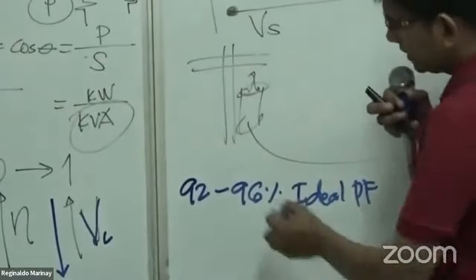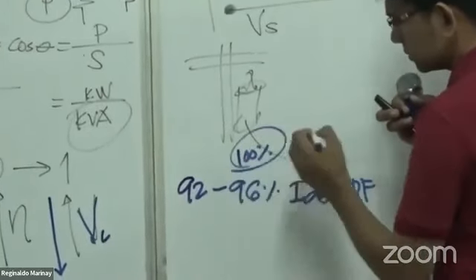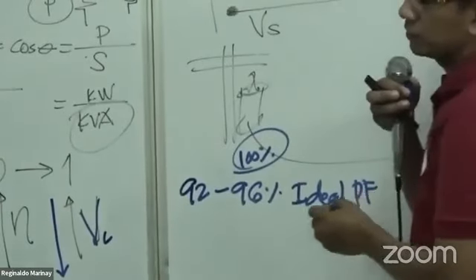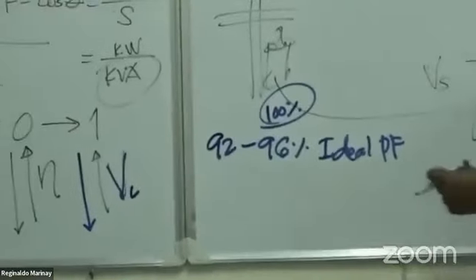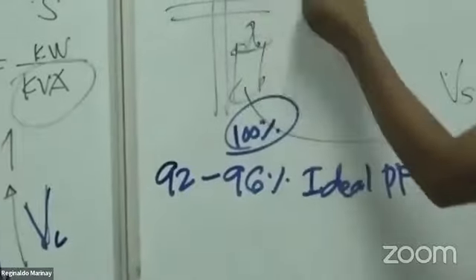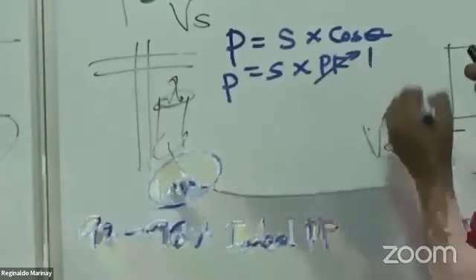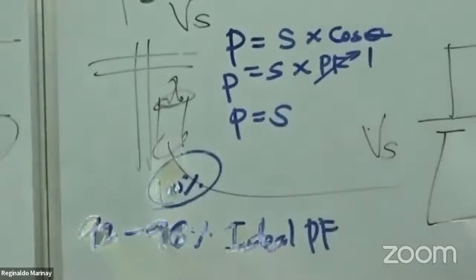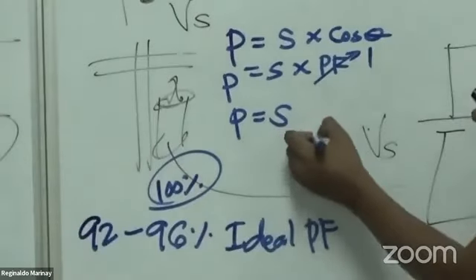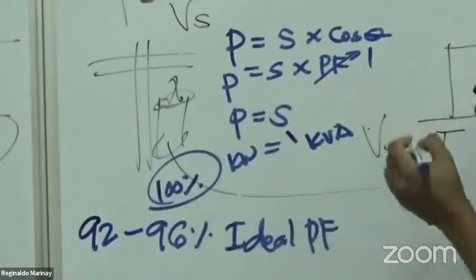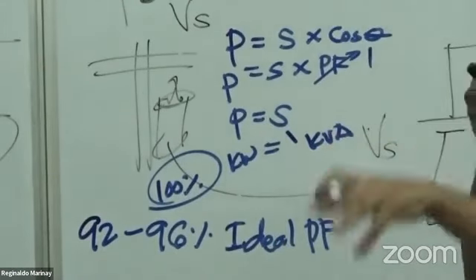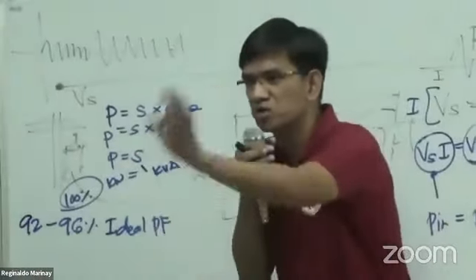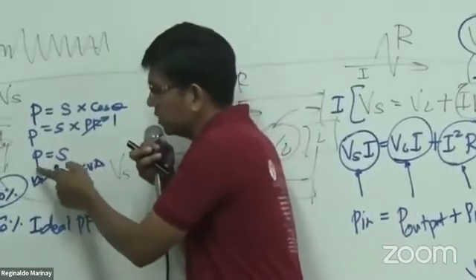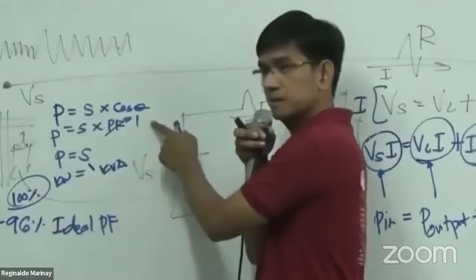Why is it not 100%? If we make the power factor 1, take a look: P equals S multiplied by cosine theta, or S times power factor. If power factor is 1, then P equals S, meaning kVA becomes kilowatts, they are just equal. Is there a Q? No more Q, because S is absolutely equal to P only, when the power factor is 1.